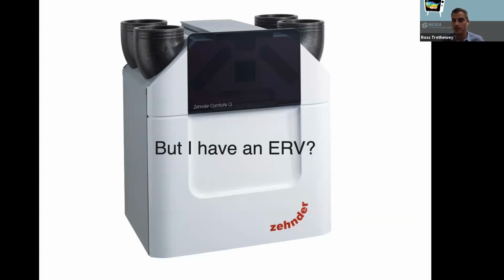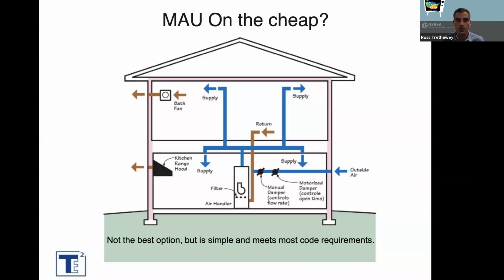So let's keep going. I don't know how we're doing on time. I get often asked, how do you do a makeup air system on the cheap? The cheapest way you can typically see it done is a motorized damper interlocked on the kitchen exhaust fan. Basically, the kitchen range becomes active, detected by a CT clamp. It triggers a motorized damper to open that lets outside air flow into the return of your air handler. And that's a common way to do it.